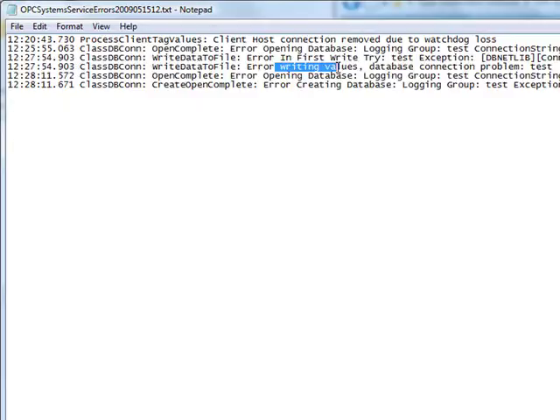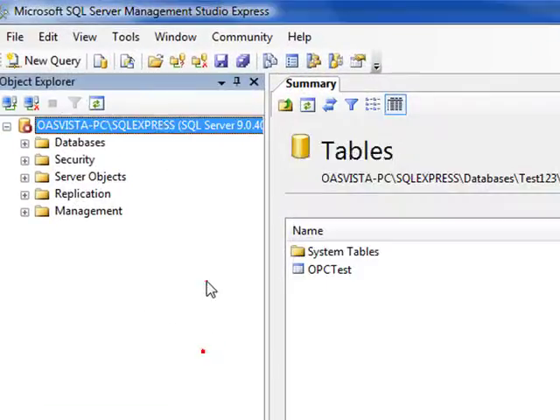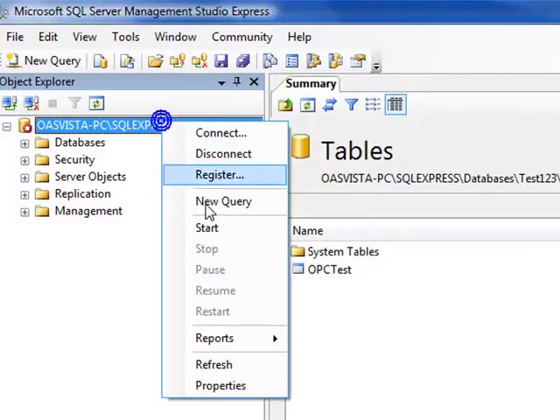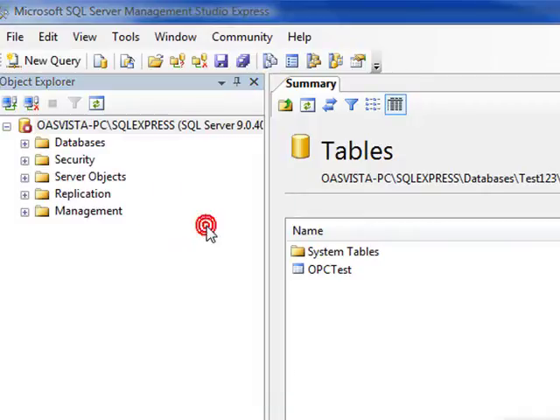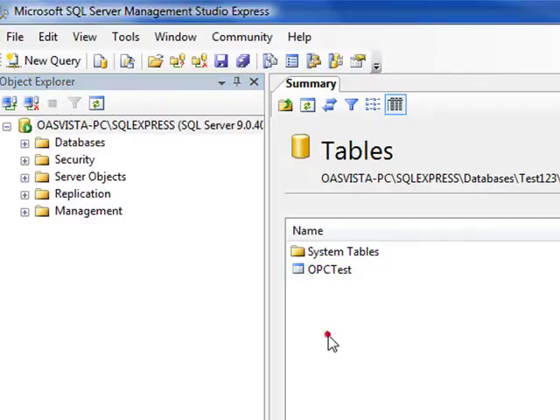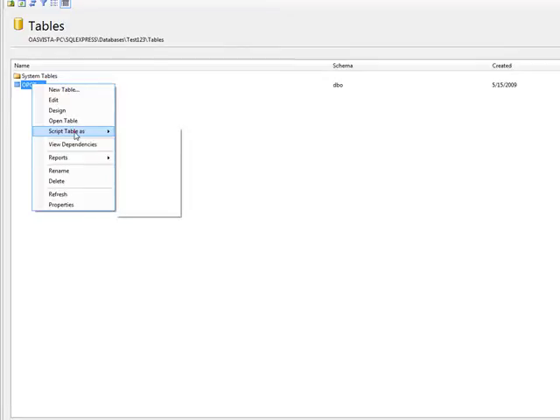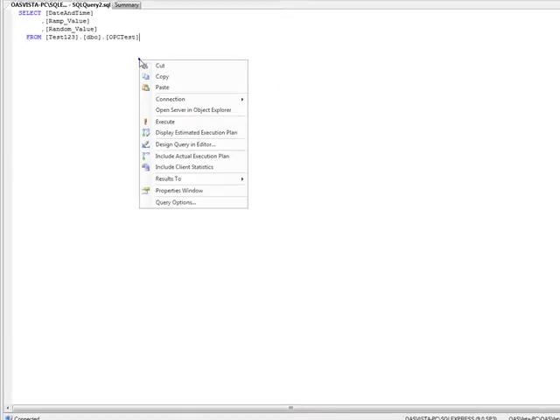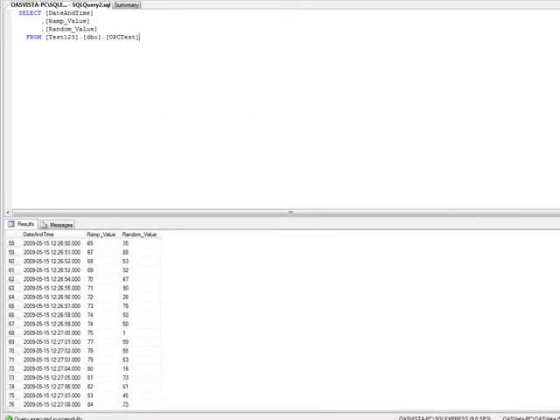But of course, at this time, we actually have a true database engine problem that can simply be resolved by starting the database engine again with the SQL Server Management Studio. During the time that we had the database engine down, the system has been buffering the data, so that when the service is then available, we have lost no data during that time that the database engine was stopped. So if we come back in and query the table again, we'll see that no data has been lost in your system.